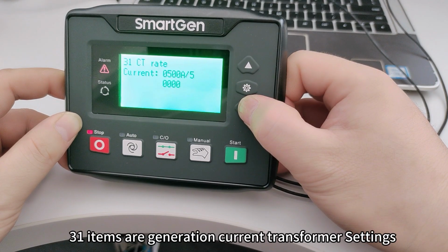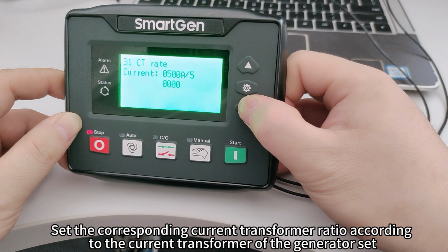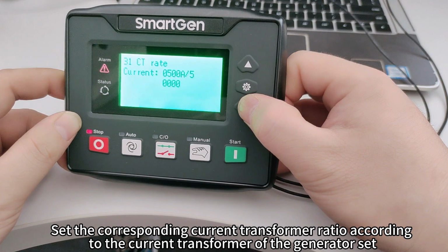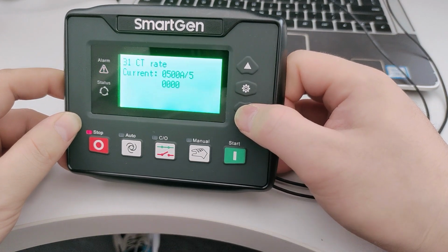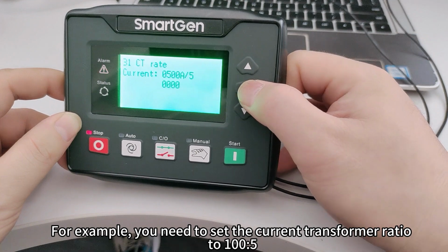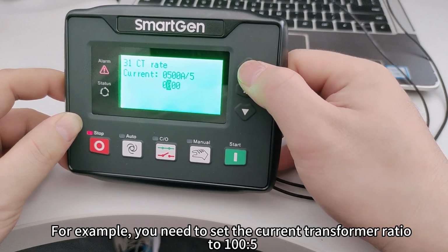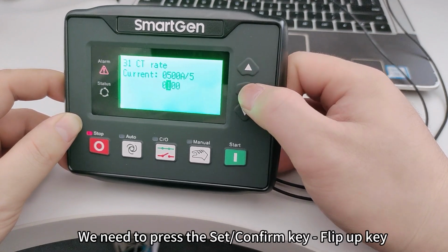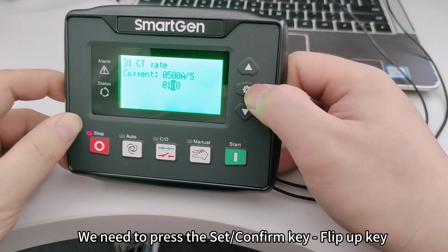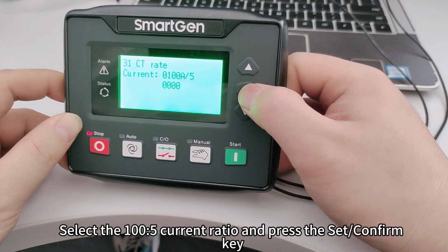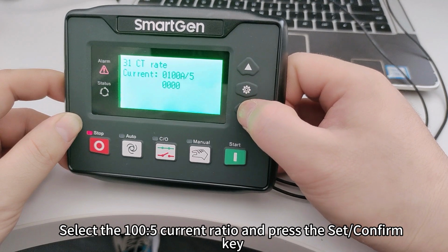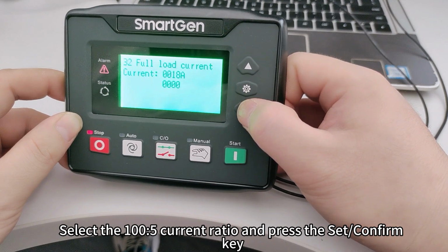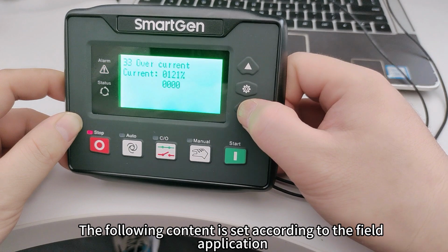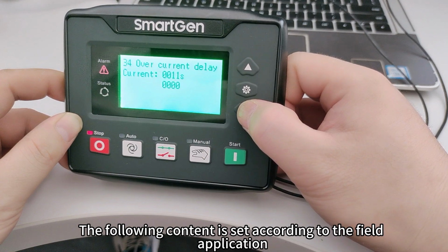Item 31 is the generator current transformer setting. Set the corresponding current transformer ratio according to the current transformer of the generator set. For example, if you need to set the current transformer ratio to 100:5, we need to press the Set Confirm key, then the flip up key. Select the 100:5 current ratio and press the Set Confirm key. The following content is set according to the field application.